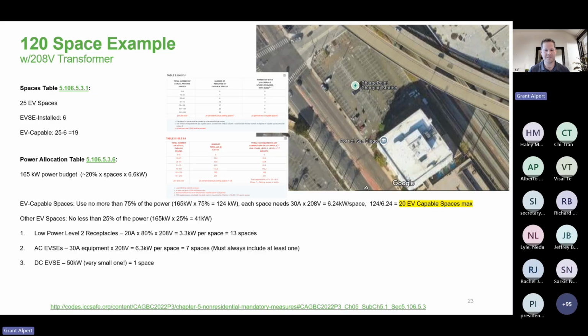And then if you want to use that 41 kilowatts for a DC charger, you can go up to 50 kilowatts, or start with 50 kilowatts, which is one of the smaller side EVSEs that is a DC fast charger, and that's one space. So lots of different options. There can be 13 spaces that are low power level 2, 7 AC EVSEs, or 1 DC fast charger. And that all meets the power budget that is required by the power allocation method, which is just one of the alternative methods to the space allocation method. So either of these are valid. It's just that the space method has been in use for longer.